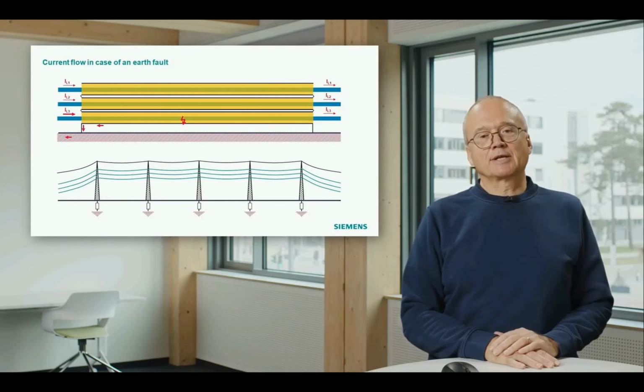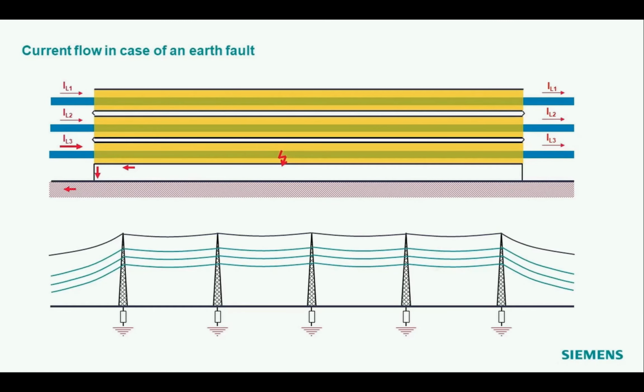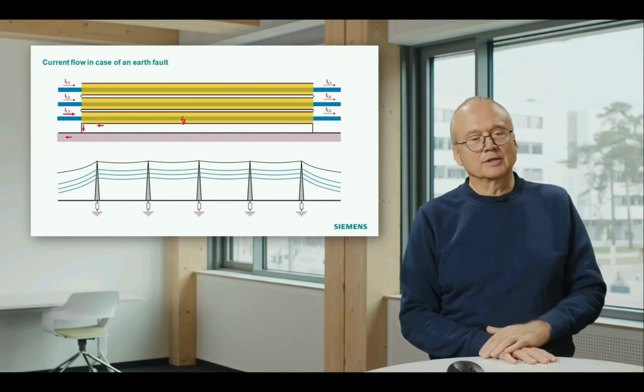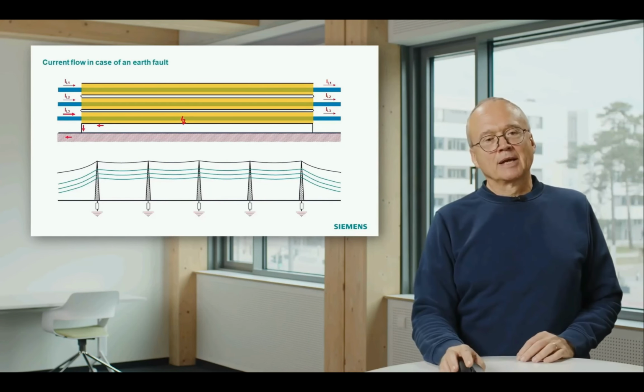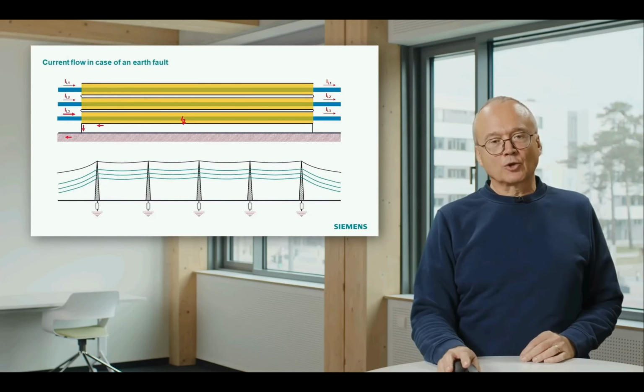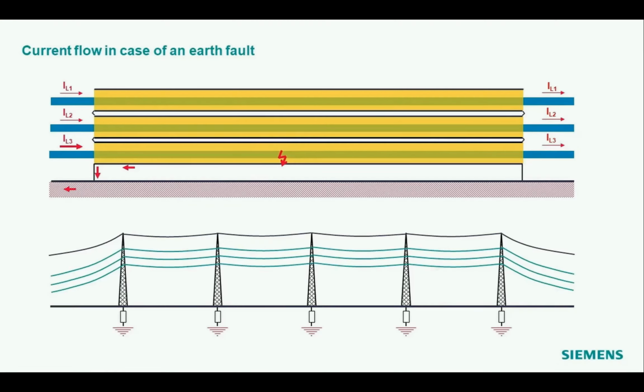Let us look at a similar example for an overhead line that is indicated in the lower part. You see here a few towers. Every tower is grounded with a certain grounding resistance. You see here in blue the 3 phase conductors, and on top is the earth conductor I already mentioned in the beginning. The earth conductor is directly connected to the tower. That means it gives an additional connection of all the towers. And now if we have a short circuit, maybe on the center tower, what is going to happen? You get this strange current flow.